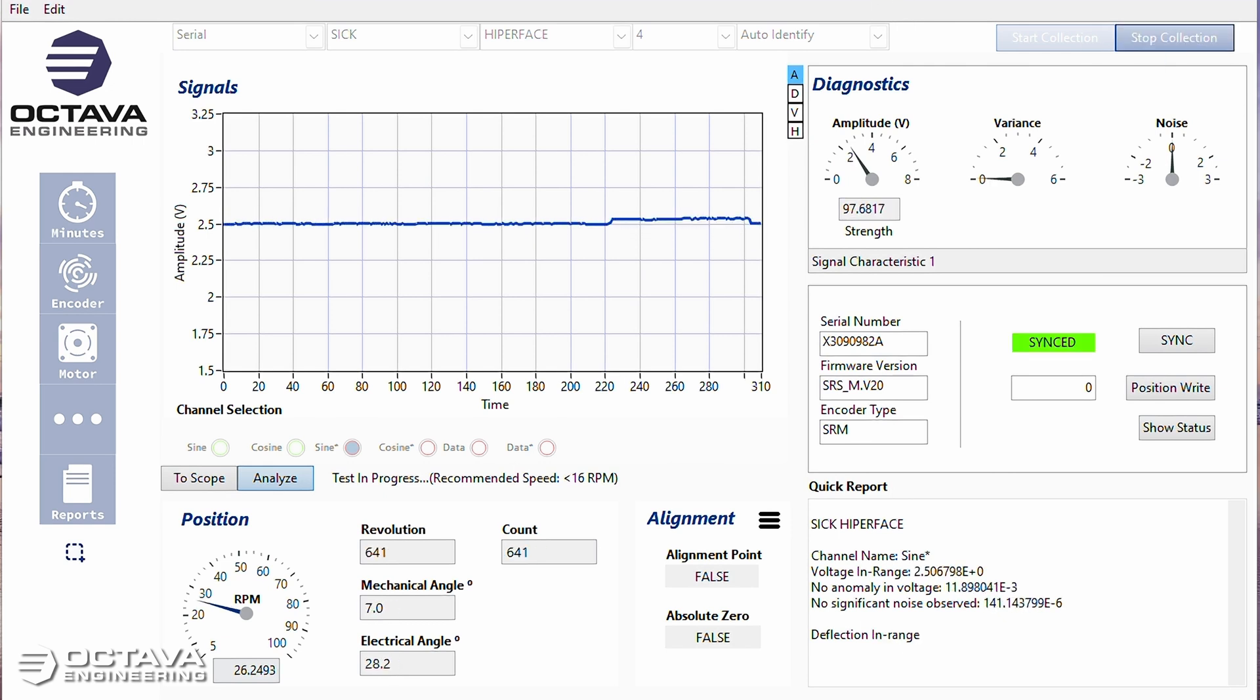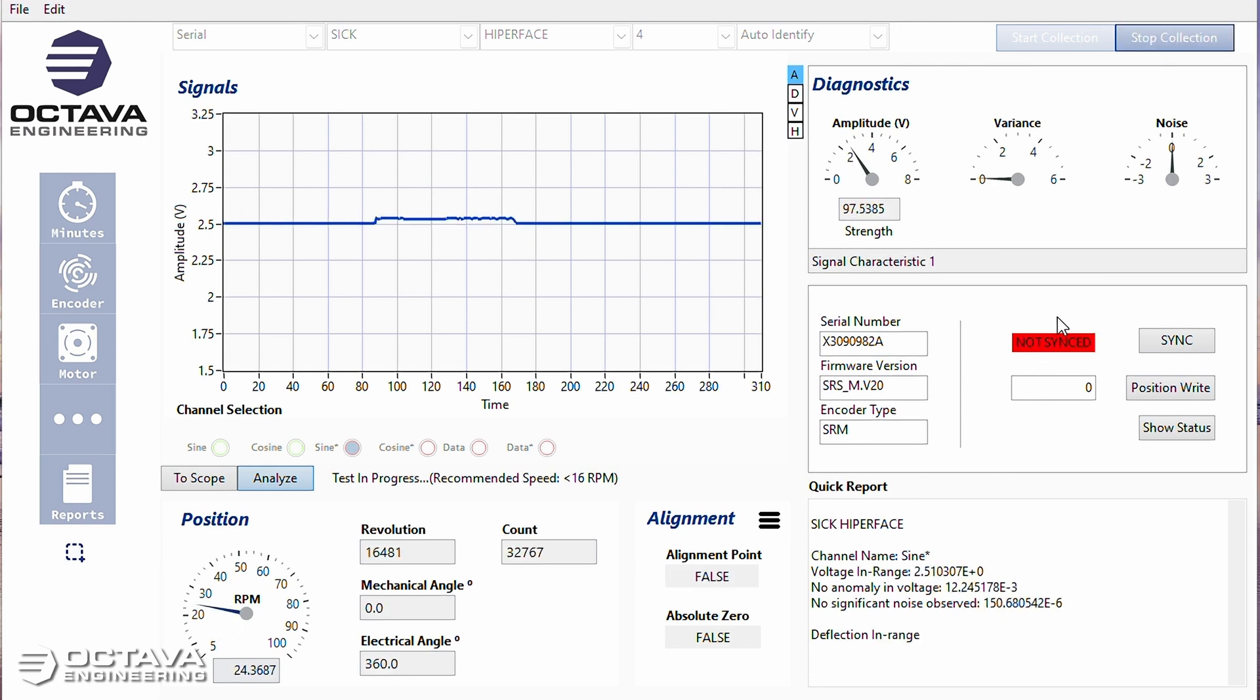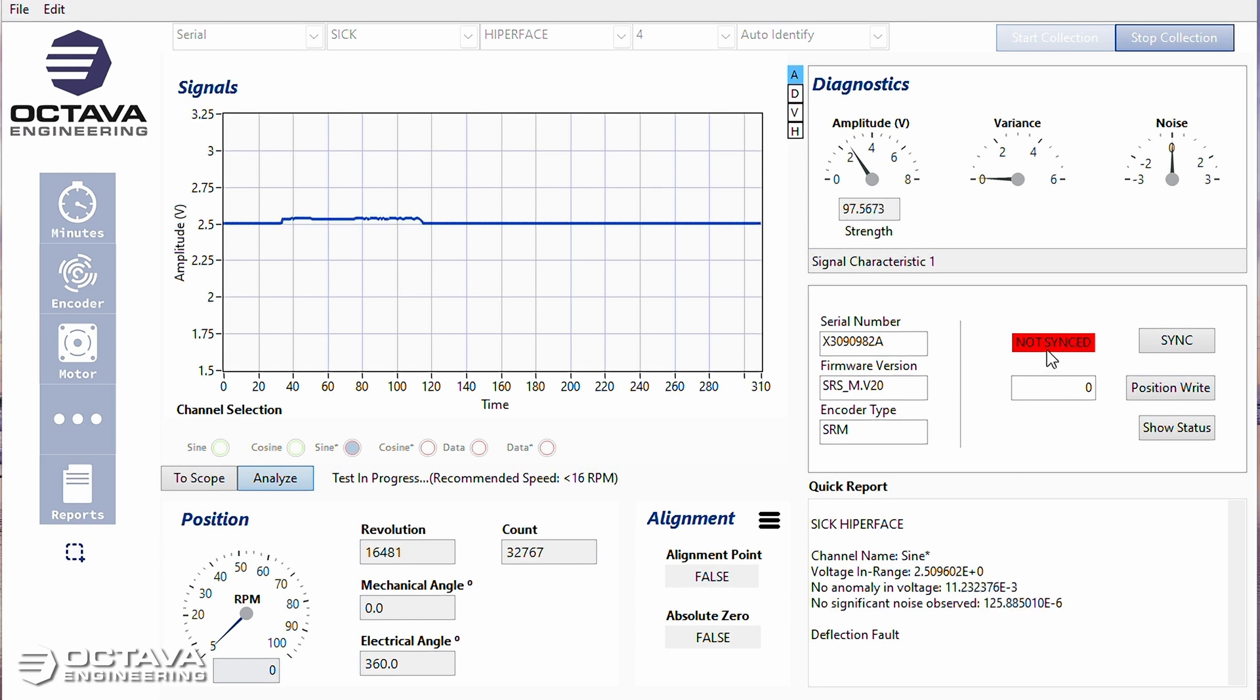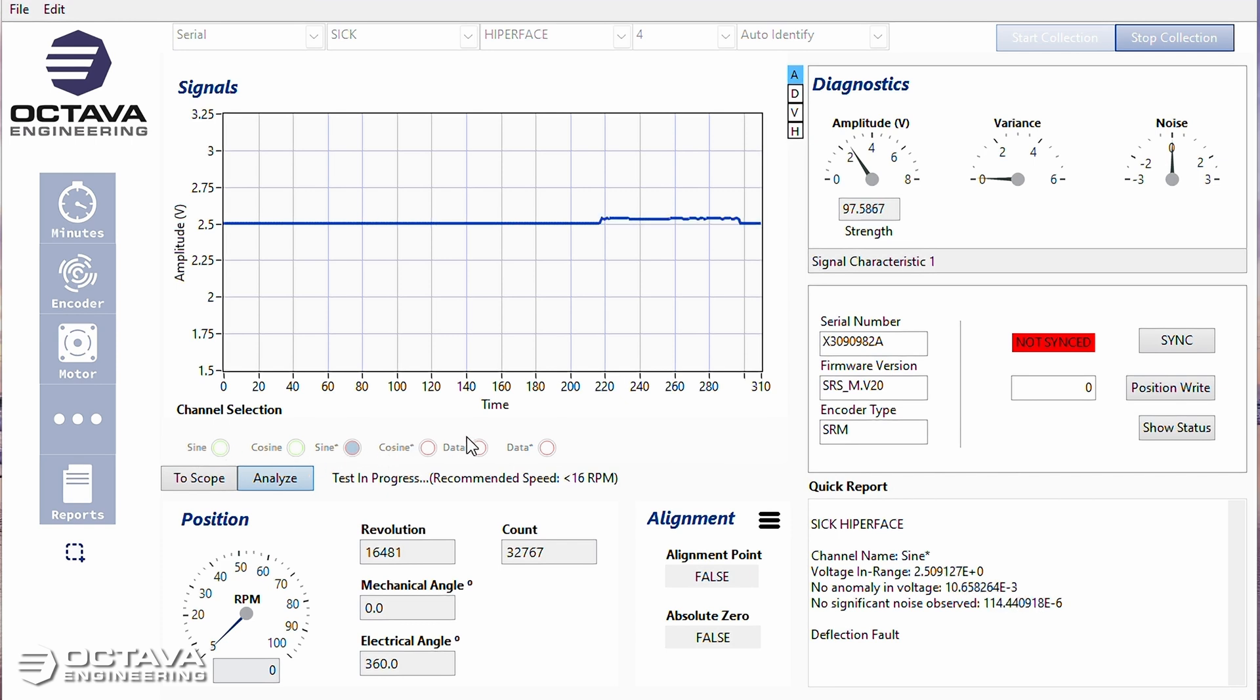The quick report is showing deflection faults. And even at the standstill, my sync is blipping in and out. So without moving the encoder, it's not synced. You can also see it's skipping through the channels way too quickly because that revolution count is not accurate.